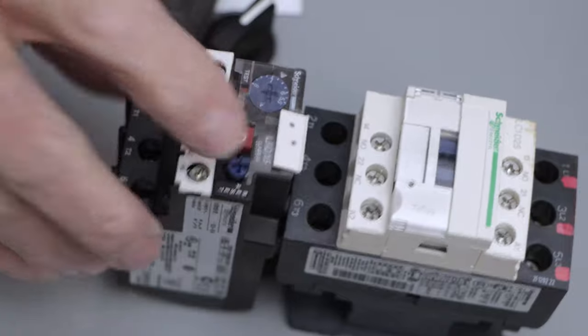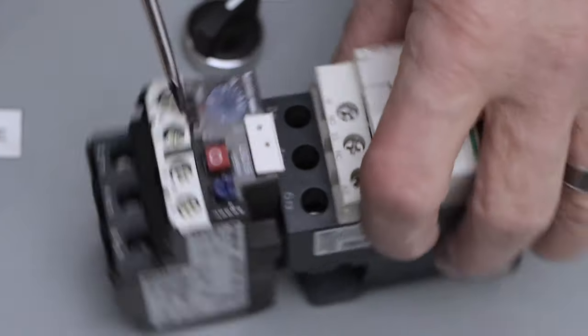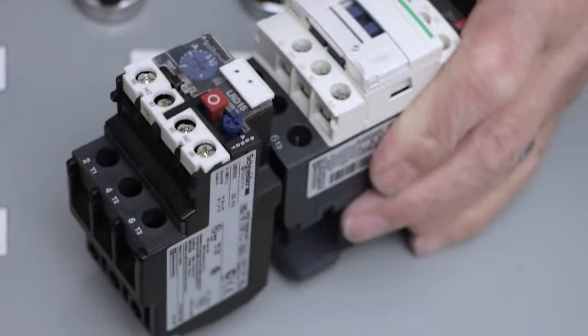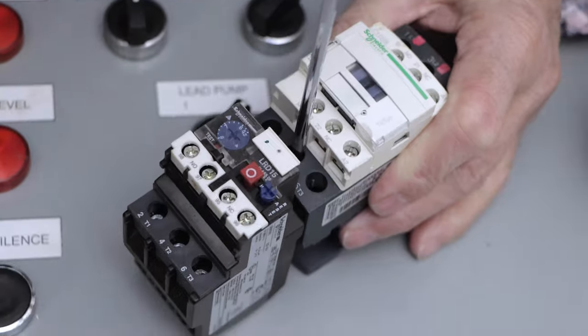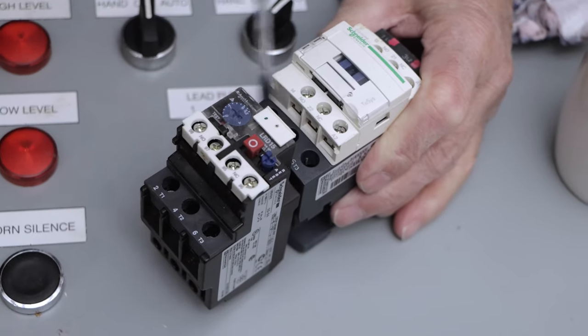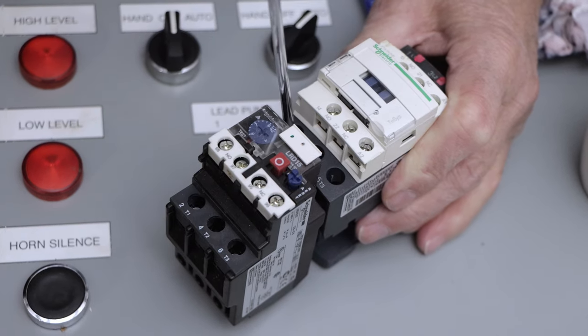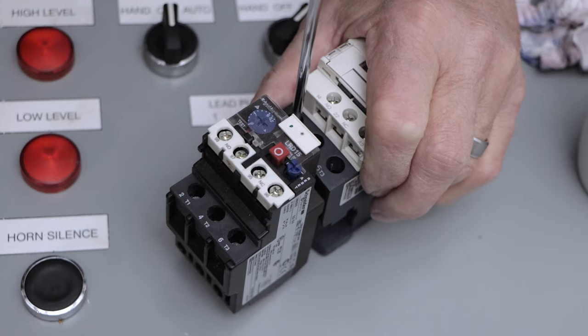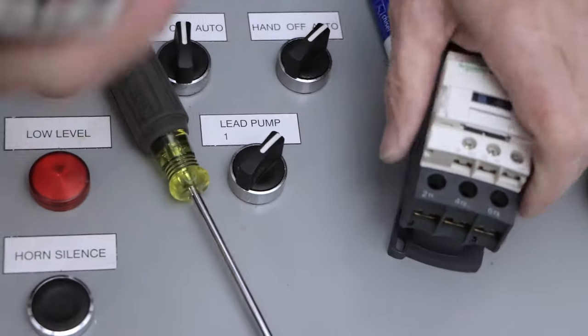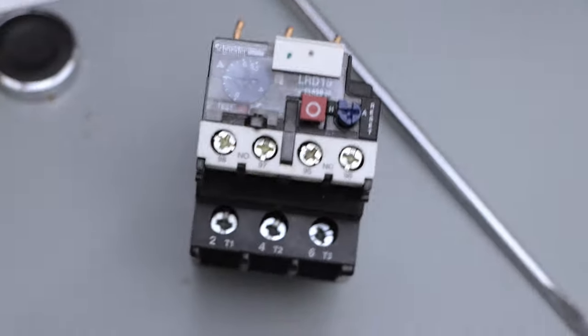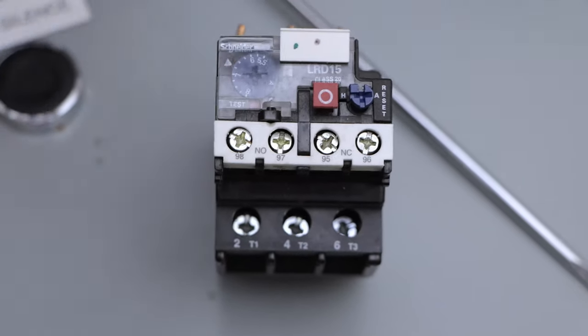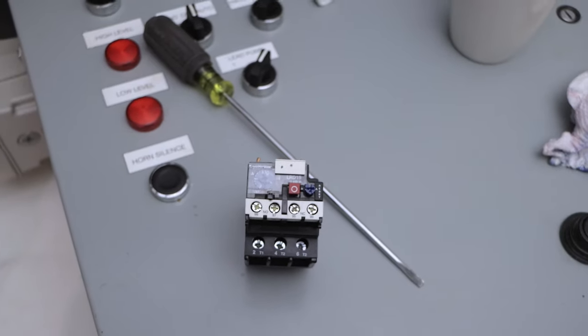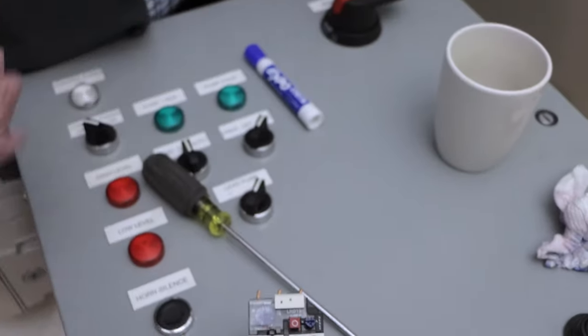This is a reset button right here, and this part here is all called the overload block. Now when you buy a Telemecanique, or that's a Schneider, but it's probably similar to a Telemecanique which we used to use. When you buy this type of IEC starter, you buy all your components individually. They will assemble them for you, but what makes it really neat is there's an overload block, and the overload block is set up for that range of current. Now if I want a heavier contactor, I can still go with that overload block, but put a heavier contactor on it, or vice versa.